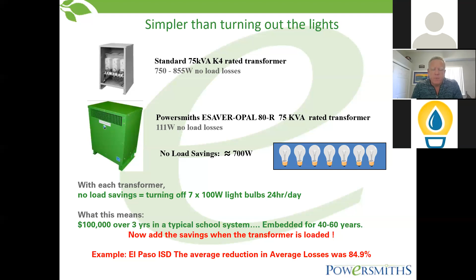So loading - what do you think the loading profiles on these transformers are? This is another study done by Catamus; we didn't do this study. This is what you see across the board. Typically they're running right around 15% loaded. That's what transformers we see all the time, about 15% loaded. So it's on the low end of the efficiency curve. That 35% really doesn't mean anything.